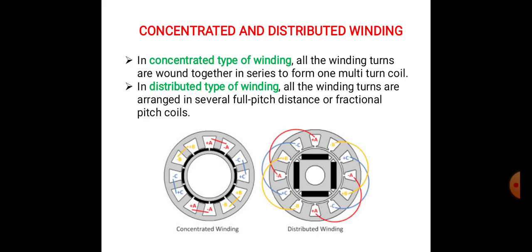On stator, windings are of two types: concentrated and distributed winding. In concentrated winding, one coil side is inside one slot under one pole, and other coil side is inside another slot under next pole. In distributed winding, conductors are placed in several slots under single pole.